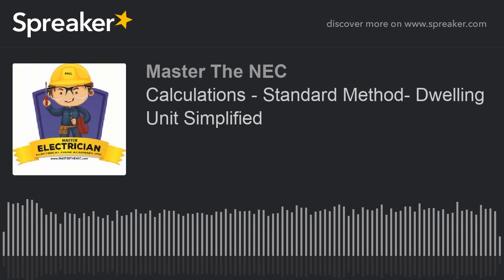Well, in our case, our clothes dryer was 4 kW. But since we're using the standard method, and 220.54 falls under Part 3, which is the standard method, and we're doing an individual dwelling unit or a one-family dwelling, then we're going to use 5,000 because that is larger than the 4,000 that is the actual one in the unit. So we take the 5,000. So the next hard value that you write on your piece of paper is 5,000. Just that simple. That's your next hardcore number. So you've got 3 numbers now written on paper. Let's go on to the next one.